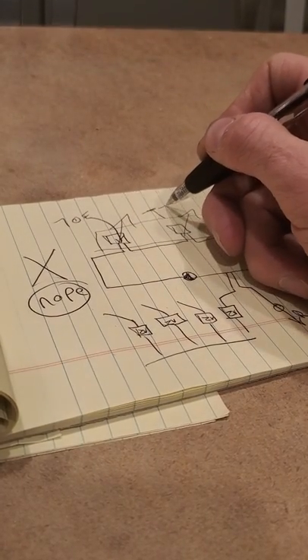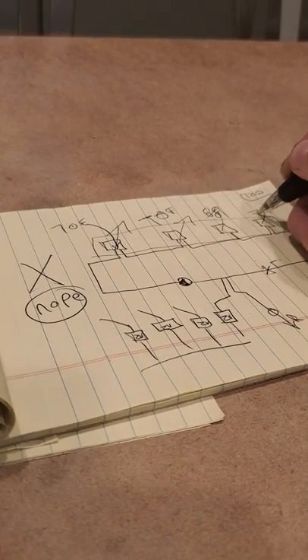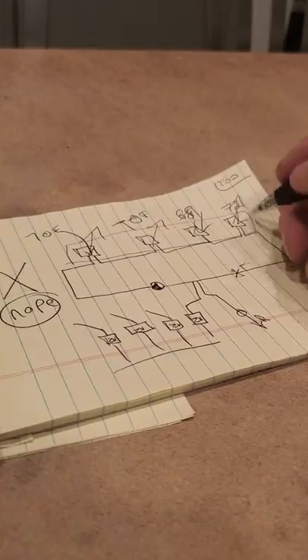This guy's 70 degrees Fahrenheit, this guy's 68 degrees Fahrenheit, this guy's 72 degrees Fahrenheit. All these temperatures are getting pushed back into the water, going back here and keeping this loop from freezing every single season. So simple, no controls to break. Everything's good to go.